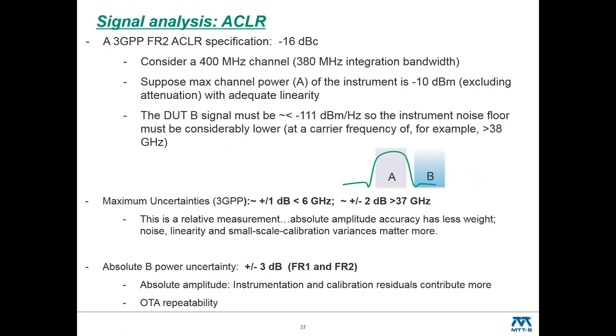So we want our instrument noise floor to be considerably lower than that. And at these frequencies, that isn't too hard to do. There are many, many instruments out there that can accomplish that. So that's encouraging. But what's new compared to some earlier standards is some maximum uncertainties are specified, plus or minus 2 dB in this higher frequency range.